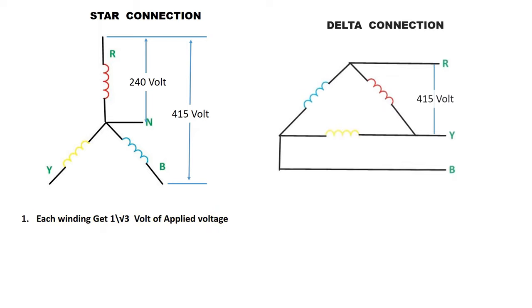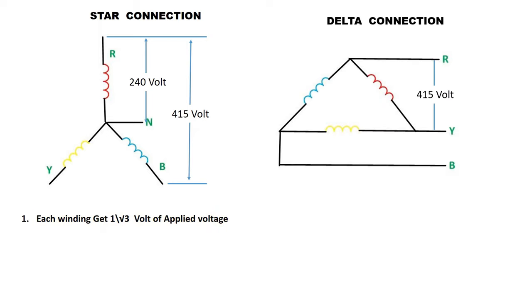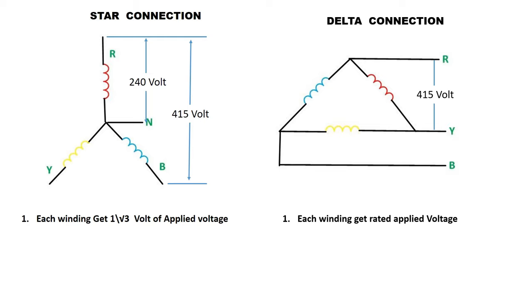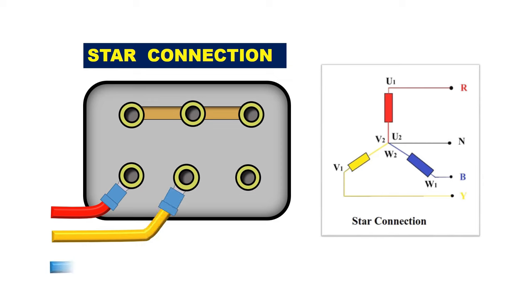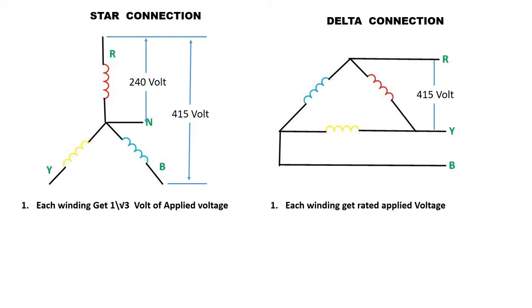If you connected this motor winding in delta, then motor winding will receive full voltage. It means even a single winding will get 415 volt. So, on connecting motor winding in star, motor winding will get less voltage. If we provide less voltage, then when we give power supply to start the motor, starting current will be only 3 to 4 times of rated current.